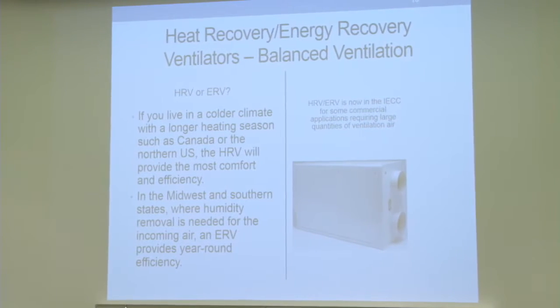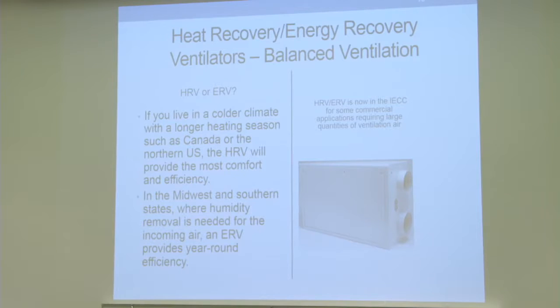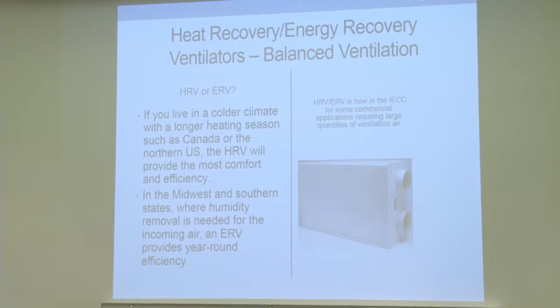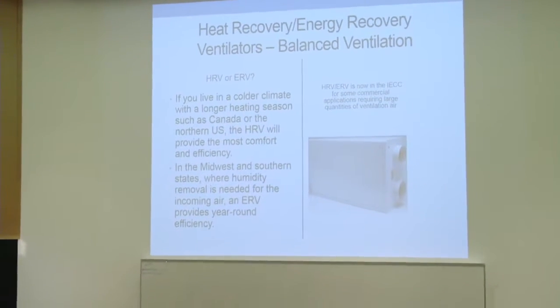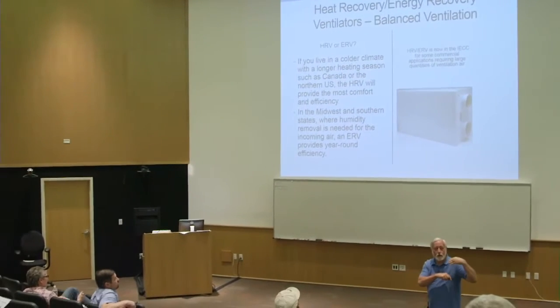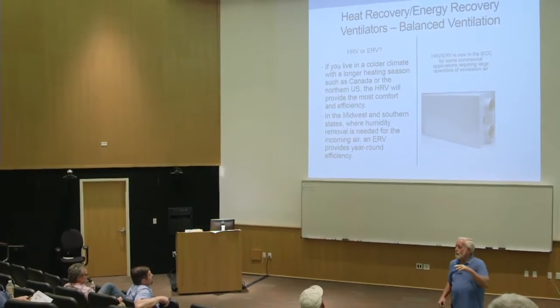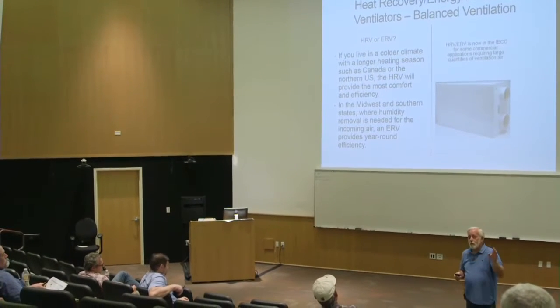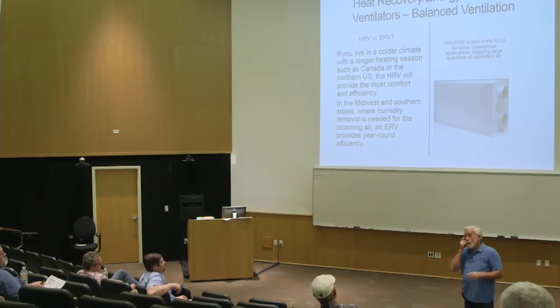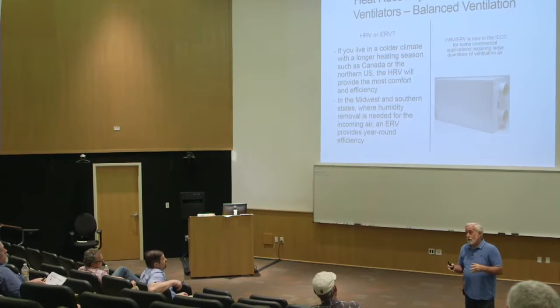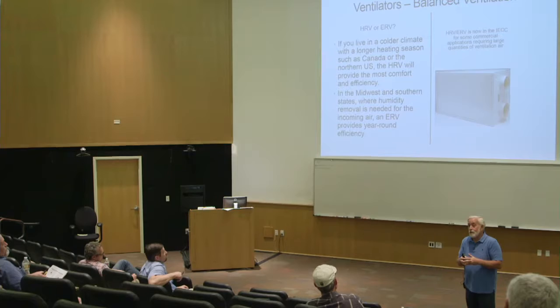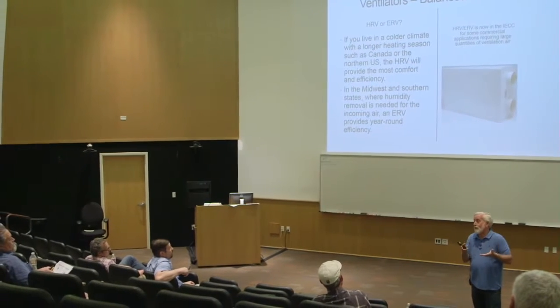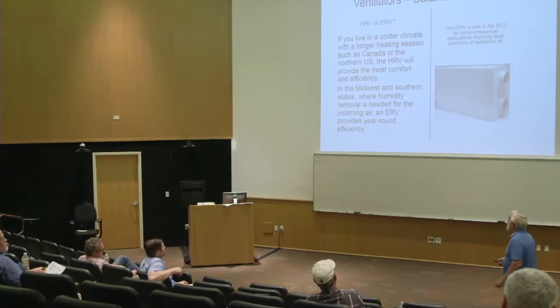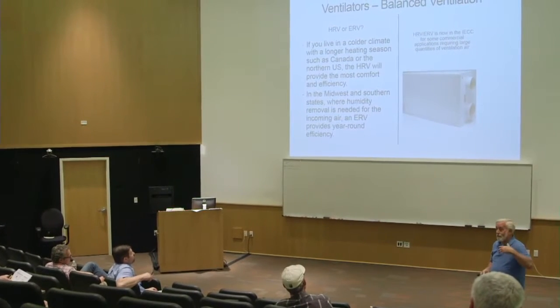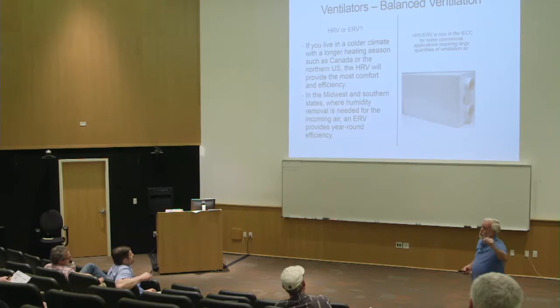I think most of you have seen it. We have heat recovery ventilators and energy recovery ventilators. Heat recovery ventilators simply recover the heat out of the air we're exhausting and use it to temper or preheat the air we're bringing back inside. They work great for removing moisture. I used them on indoor pools all the time because they remove moisture. But they're not always the best thing in Utah in a home, because guess what you do? You suck the humidity out that you're trying to keep up to a comfortable level. And so we have ERVs that do bring moisture in from outside or take our moisture out.